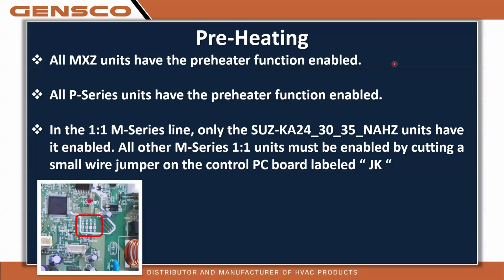You'll find it on the control board, and this is going to be in the units that only have one board. The small SUZs, even the hyperheat SUZs under 24,000, any M series MUZ or MUY that has the one board function, you have to look for this JK jumper prior to turning power on and cut that jumper.